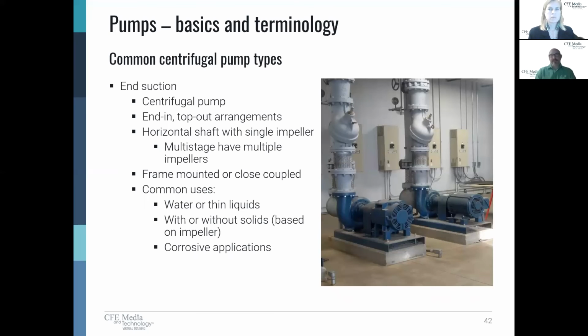Now here we're going to see, look, I got VFDs along the back wall. But again, the mechanical engineer needs to tell the electrical engineer, where can I physically put these? Now, end suction pumps are very common, right? I see them a lot of times in cooling tower applications. And they're great for chilled water. They can handle very large pump sizes and very large pipe sizes as well. 10, 12, 14, 16 inches is very common.